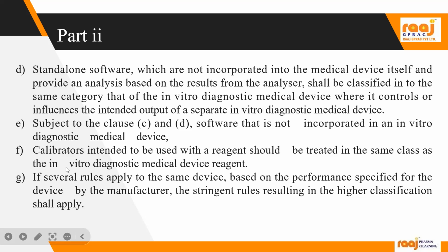Calibrators intended to be used with a reagent should be treated in the same class as the in vitro diagnostics. Sometimes they will use the reagent solution. In that case, it can be treated in the same class as the in vitro diagnostic medical devices, if calibrators are used. If several rules apply to the same device, this also we have seen, right? Based on the performance specified for the device, the higher classification only. For class D, we have to see the more stringent rule, the higher classification.